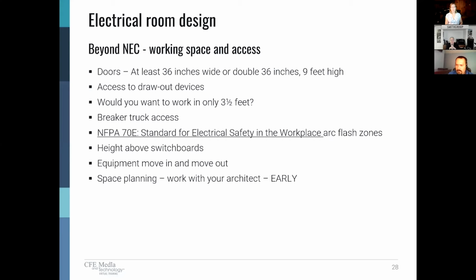In my mind, when you've got switchgear, which we talked about being the primary type of system that has draw-out devices versus switchboards, you want to make sure that when those breakers are drawn out, you can still get past them to one of the other doors. That's just good engineering practice, that you still have clearance, that it doesn't block your access.